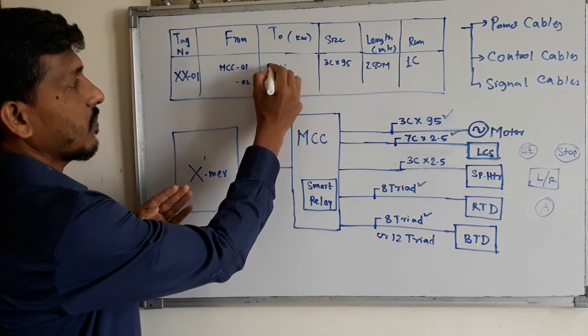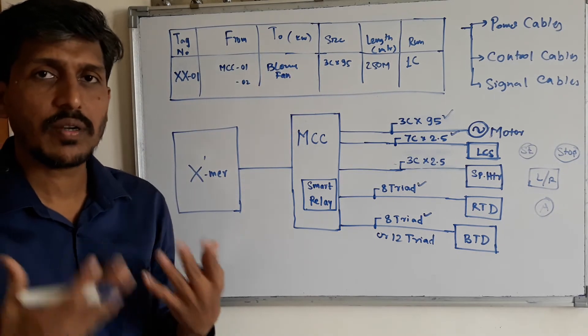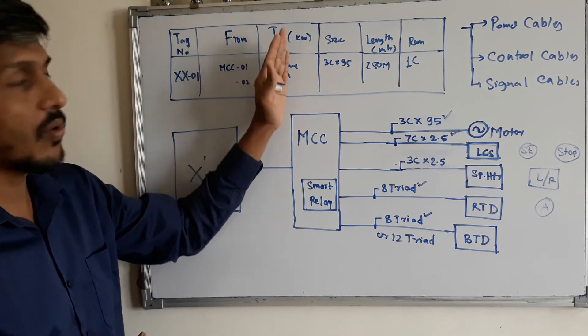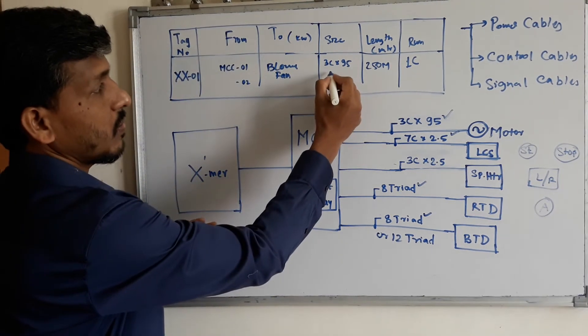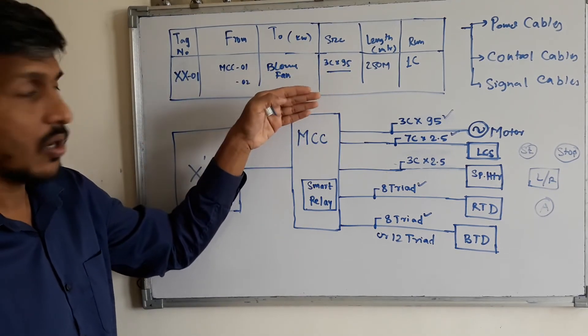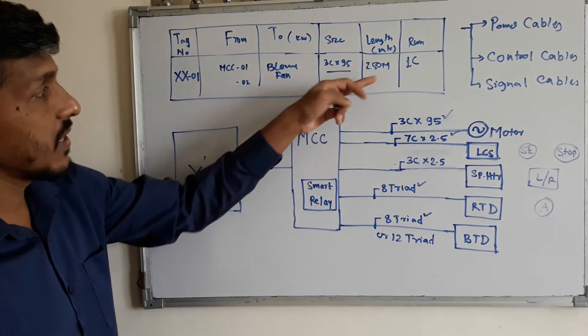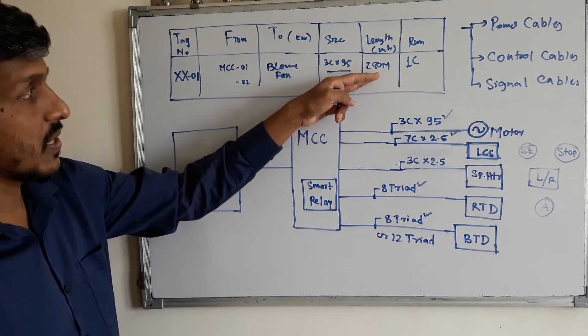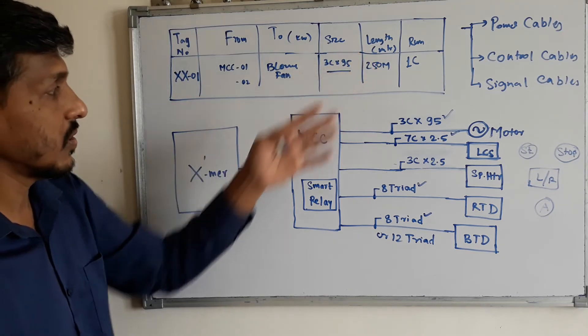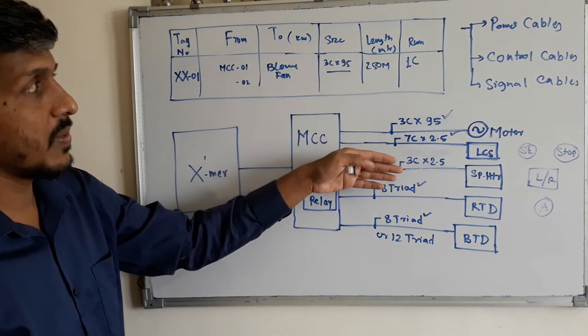From the tag, you mention where the cable is routed — from the MCC to the motor end. You can give a description such as 'blower motor' or 'fan motor' depending on the type. You then mention the cable size, such as 3-core 95mm² for a power cable, 7-core 2.5mm² or 3-core 2.5mm² for control, or an 8-triad signal cable. You also include the cable length — for example, 250 meters or 100 meters — representing the distance from MCC to motor end.